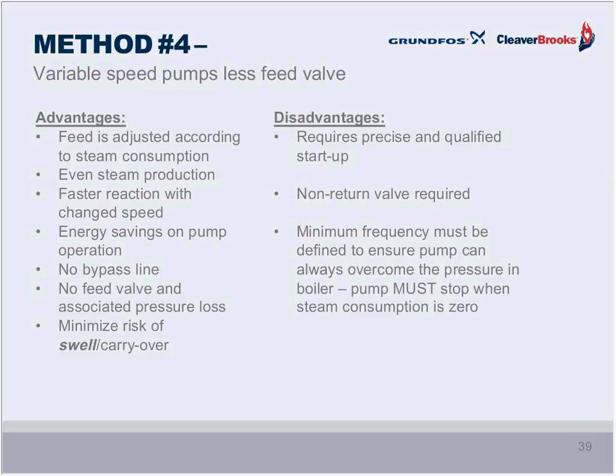You have to have a technician that really understands what's going on here. You do have to put a check valve, a non-return valve, in the line. And we won't go into too much detail on this, but there has to be a minimum frequency defined to ensure that the pump can always overcome the pressure in the boiler. But the pump also has to be capable of stopping when steam consumption is at zero. So it takes some skilled technicians to set this up and get it running properly.